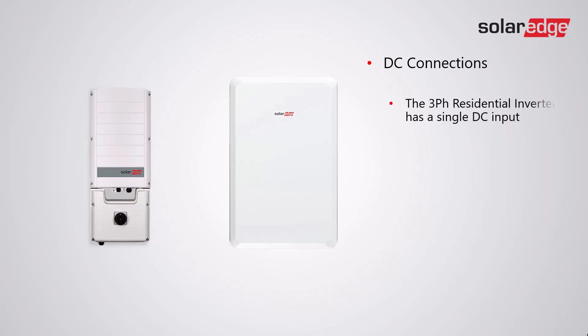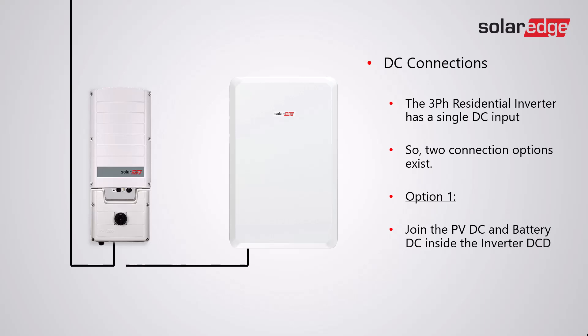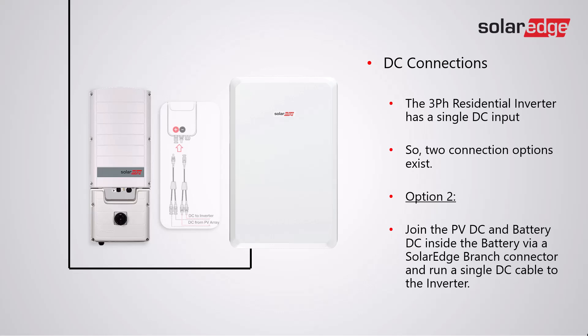The three-phase residential inverter has a single DC input, so two connection options exist. Option one: join the PV DC and the battery DC inside the inverter DCD. For option two: join the PV DC and the battery DC inside the battery via the SolarEdge branch connector, and run a single DC cable to the inverter.